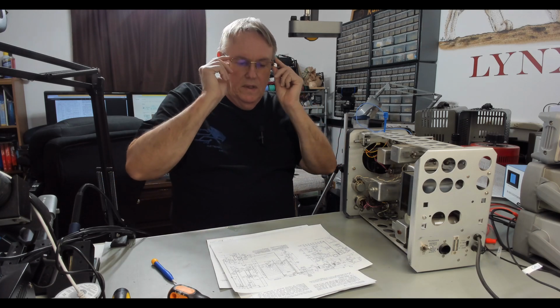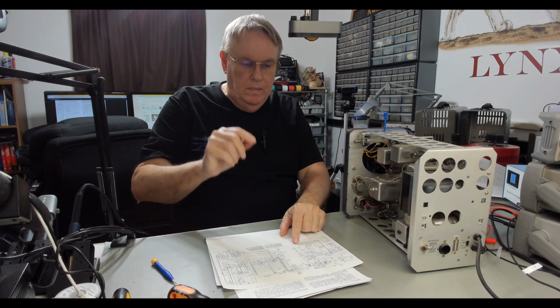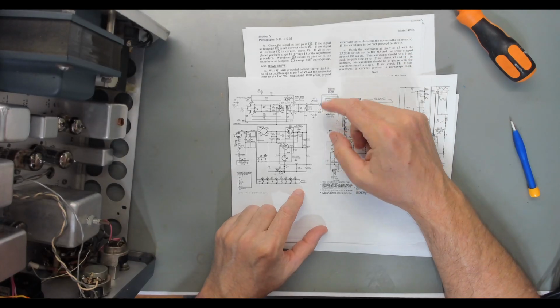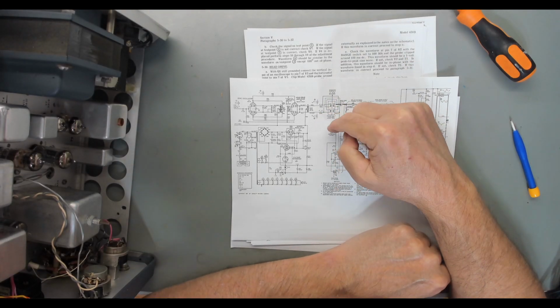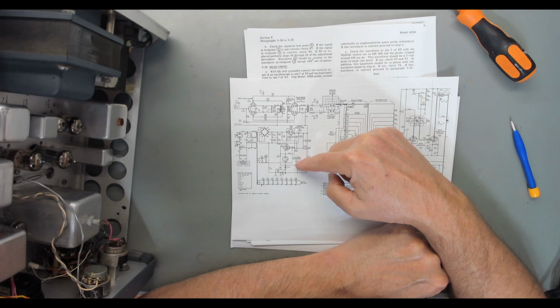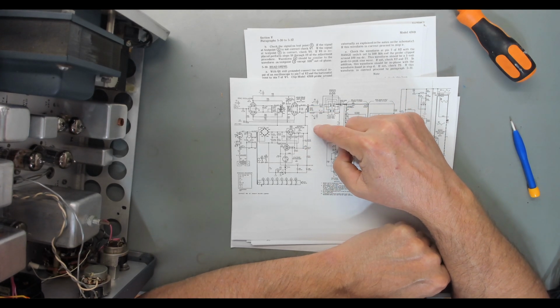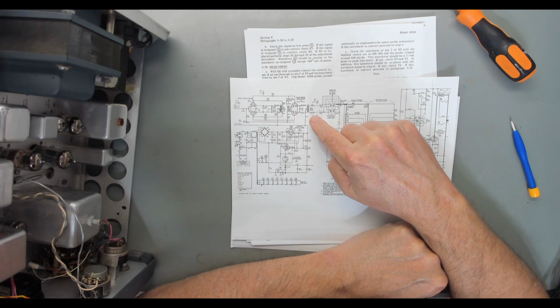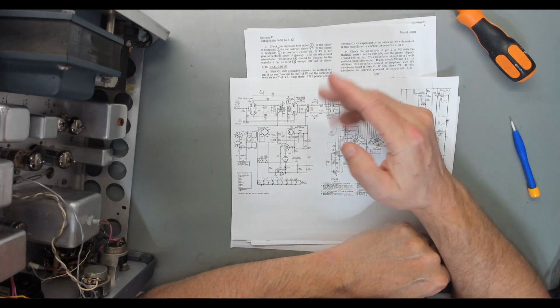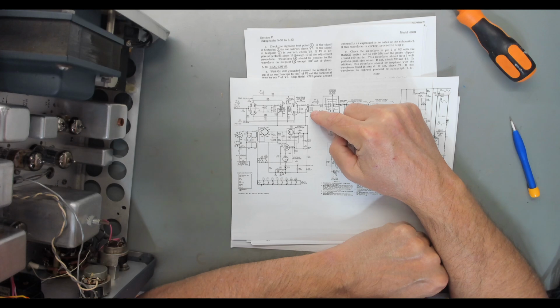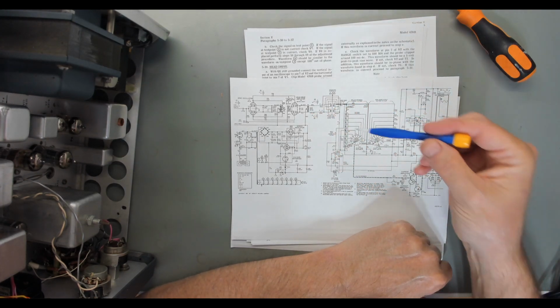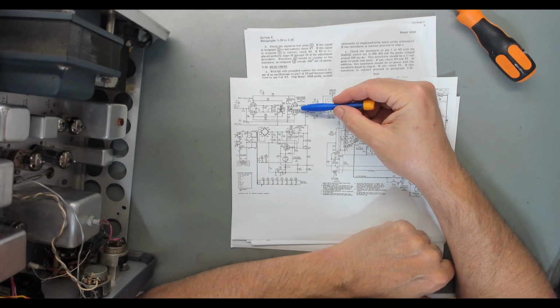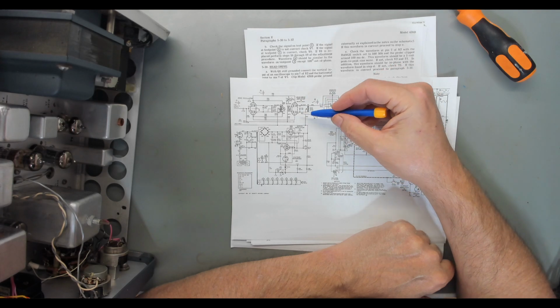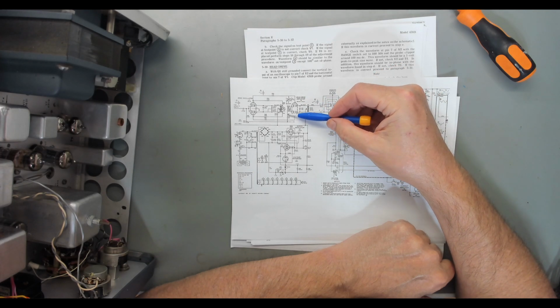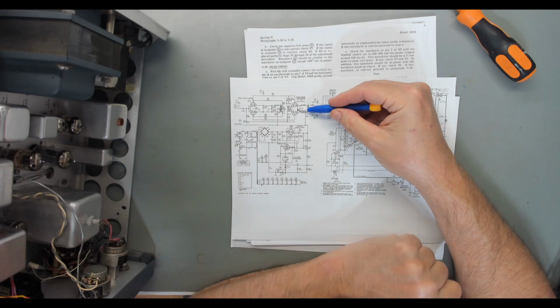So okay, I've looked at this from a bunch of different angles, and here's what I've come up with. Since we've got good signal on one side of this transformer output from the oscillator down here in the amplifier, the head amplifier is putting out a signal, a good signal we know, at least on the one side. There's a drive amp balance pot, which I played with and had no effect whatsoever.